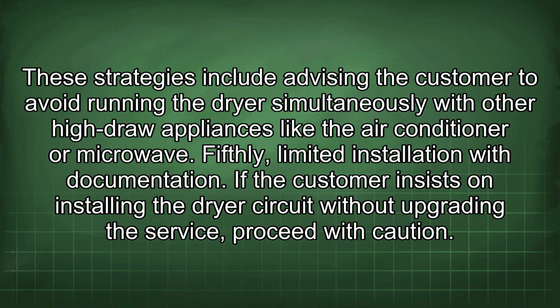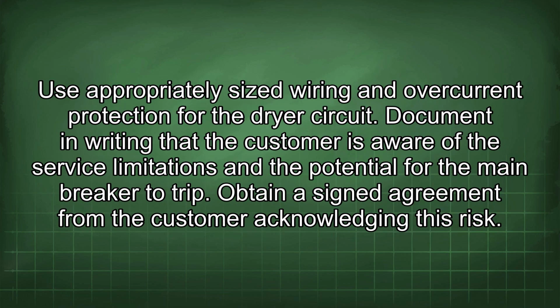Fifthly, limited installation with documentation. If the customer insists on installing the dryer circuit without upgrading the service, proceed with caution. Use appropriately sized wiring and overcurrent protection for the dryer circuit. Document in writing that the customer is aware of the service limitations and the potential for the main breaker to trip. Obtain a signed agreement from the customer acknowledging this risk.